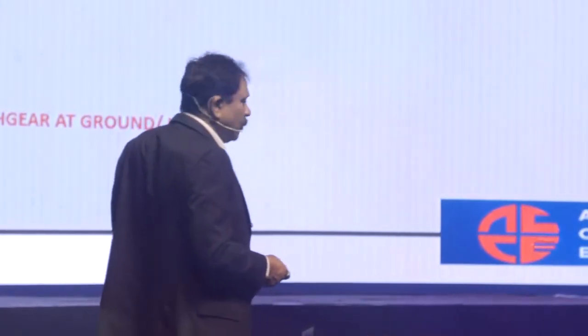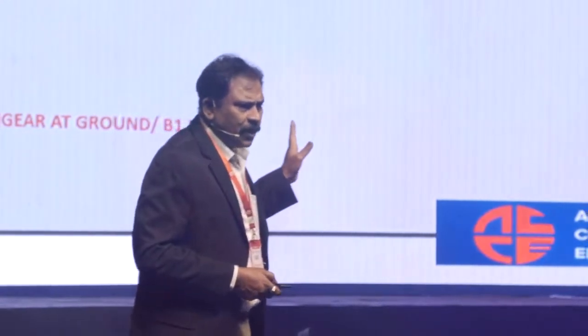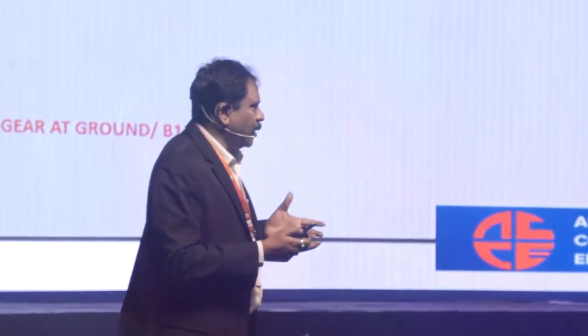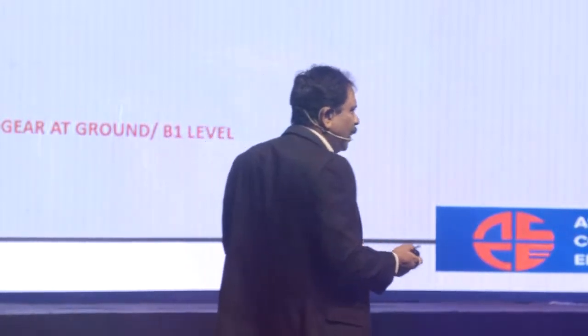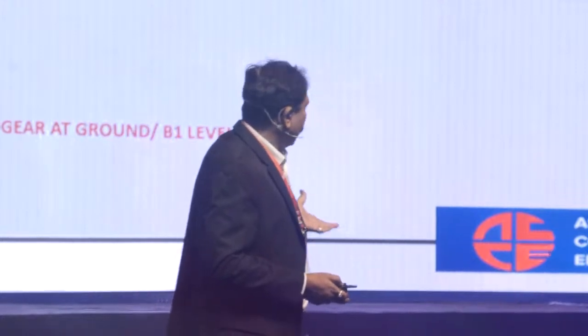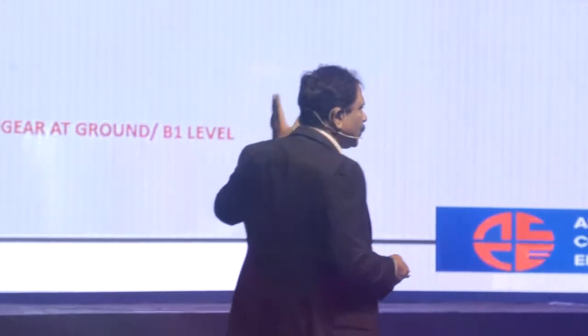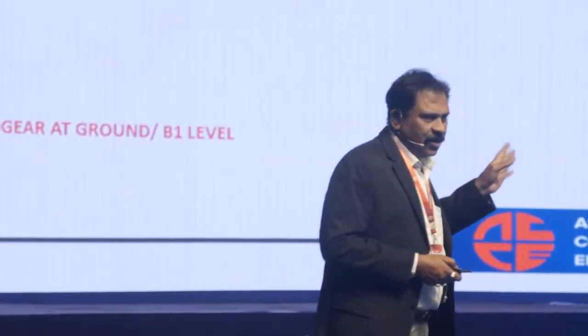So if you look at a tall building, generally, I mean, if you look at Burj Khalifa, it has got 64 transformers across various levels. We can't distribute the power for a 900 meters or 850 meters building right from ground level, because there will be a lot of losses in the distribution. So naturally, we'll have some transformers at the ground, and then we'll have 11 kV cables which are taken up to the various levels, and the 64 transformers of 1 megawatt range each one are all located at various floors.